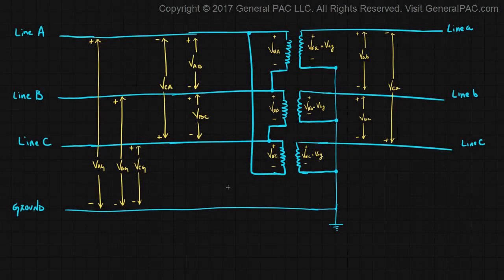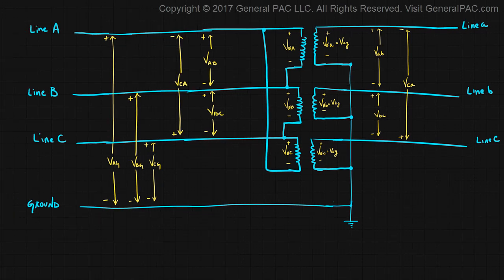In the previous videos, we drew this diagram and really understood all of the pieces and how they all work together. What we concluded was that VAG on the high voltage side is used as a reference quantity, and we're comparing that to VAG on the low voltage side, which is also used as a reference. These two pieces of information are critical, and what we ended up doing was drawing a phasor diagram.